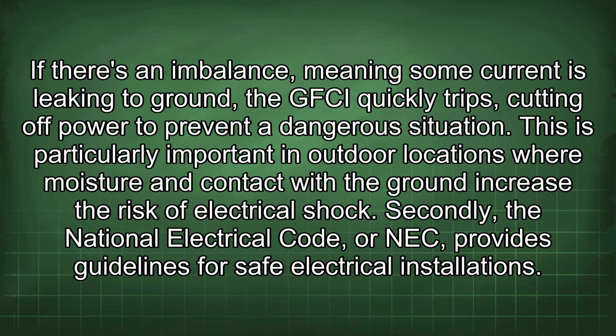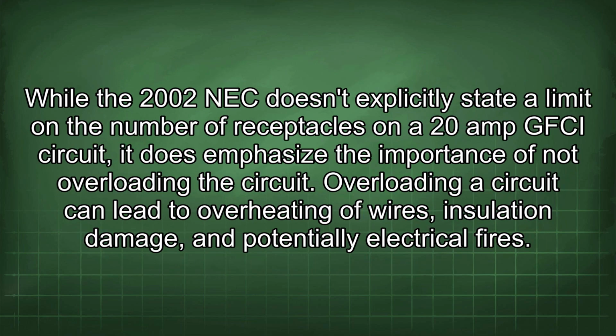Secondly, the National Electrical Code, or NEC, provides guidelines for safe electrical installations. While the 2002 NEC doesn't explicitly state a limit on the number of receptacles on a 20-amp GFCI circuit, it does emphasize the importance of not overloading the circuit. Overloading a circuit can lead to overheating of wires, insulation damage, and potentially electrical fires.